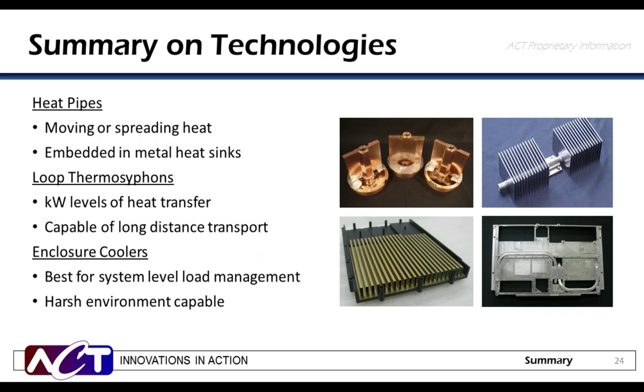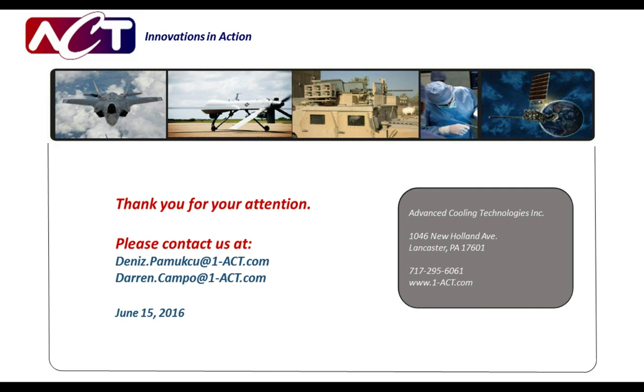To summarize the three technologies: heat pipes are discrete devices for moving and spreading heat, traditionally embedded into metallic heat sinks. Loop thermosiphons are used when you have much higher kilowatt-level heat loads to transfer, and they're capable of moving heat long distances. When you're not trying to manage a discrete device on its own, consider an enclosure cooler — these are best for system-level loads, and in harsh environments, they may be your only option. Thank you for joining our webinar.